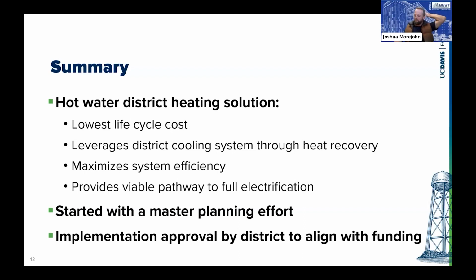The process we went through, to summarize, was looking at the lowest life cycle cost for our heating system. It became very clear during master planning that hot water with centralized heat recovery was by far the lowest life cycle cost for us. There are a lot of ways to tap into low temperature heat sources with that type of system, including your cooling system. Overall system efficiency goes through the roof, and it provides a pathway to full electrification.